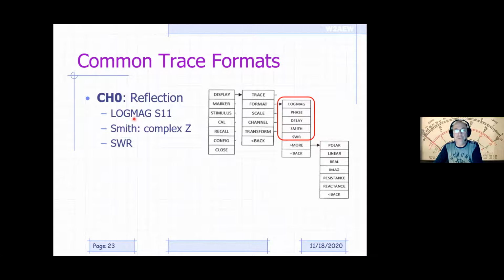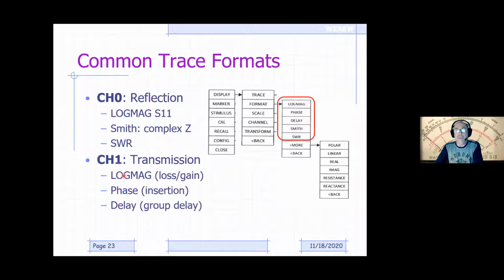So channel 0 is typically log mag of S11, Smith chart for complex impedance, or linear SWR. For channel 1, the transmission measurements, again, is typically the log magnitude or insertion loss, which will be S21, or phase or delay measurements. So those are the most common ones that you'll have. There are other formats available. If you're kind of into RF design and things like that, some of these might be important to you, but I'm not going to go through them in detail here. But lots of different formats available for you. This transform function that's here is the thing that we use to measure distance to fault or length of a transmission line, for example.